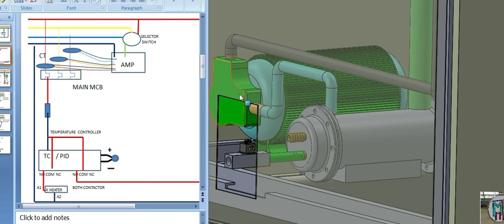We cannot stop this circulation motor at any time. The circulation motor must run every time. If you stop this motor, the circulation of your thermic oil will stop, and your heating will not be uniform in your tank. So we have to watch every time whether this is working or not. We will take the precaution that this contactor is ready and in starting position or not. We will take an interlock of this contactor in our system when we start our transfer pump, and the transfer and loading pump we will also explain in another video.